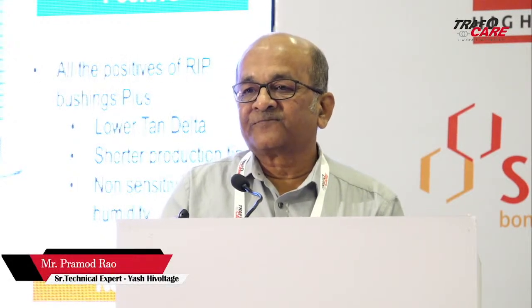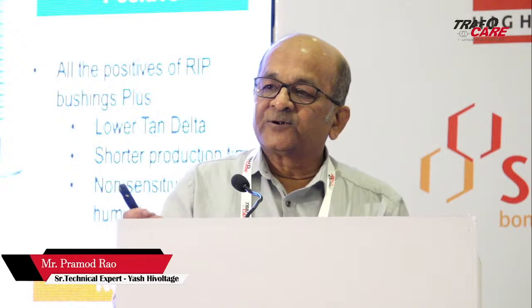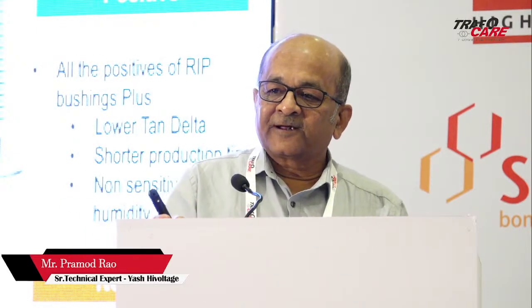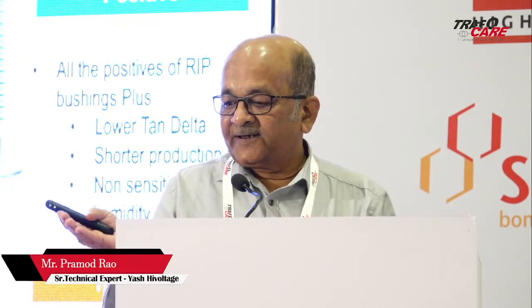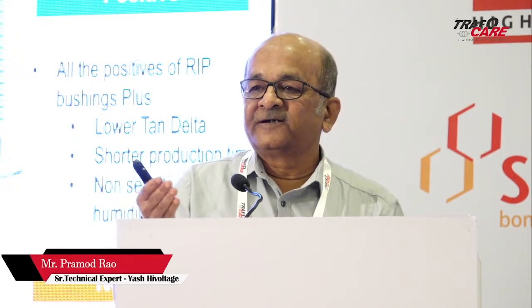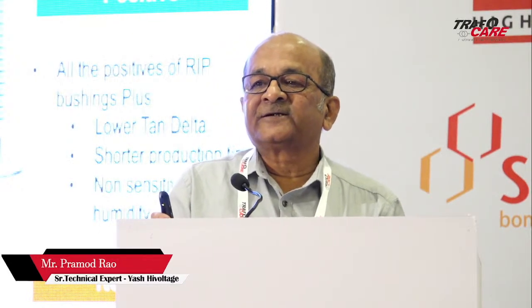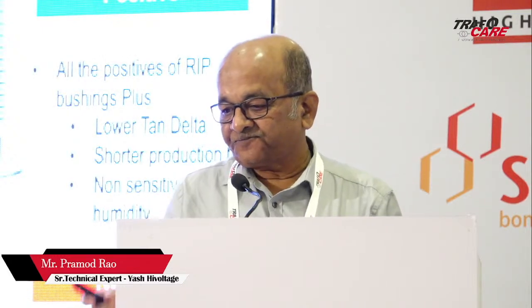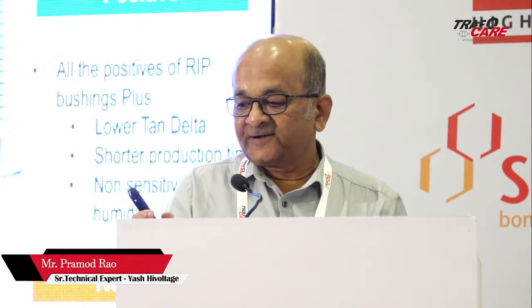The third one, what you see, is RIS. All the positives of RIP do exist in this, but it is a paperless bushing. It involves synthetic film. You will see the picture of the synthetic film in the next slide. It has a lower tan delta value compared to RIP. Then it has a shorter production time because paper needs to be dried. A synthetic film doesn't need drying. Then it is non-sensitive to humidity, even if it is stored in a humid environment.